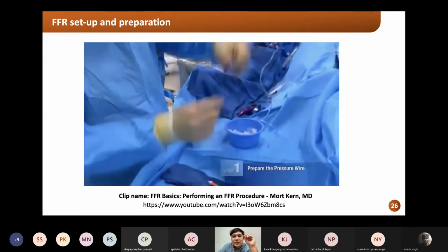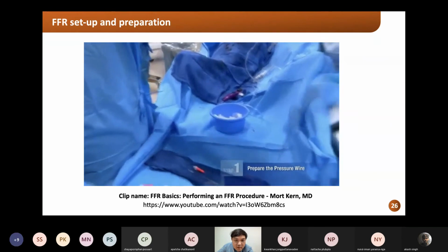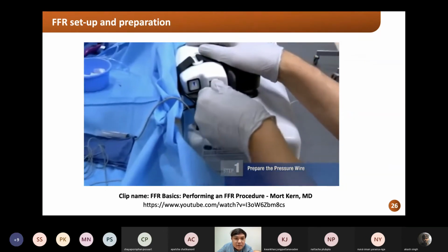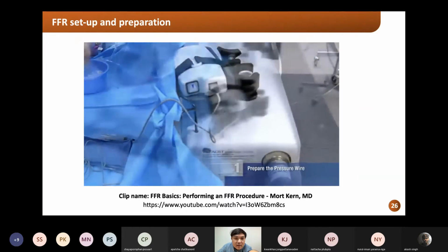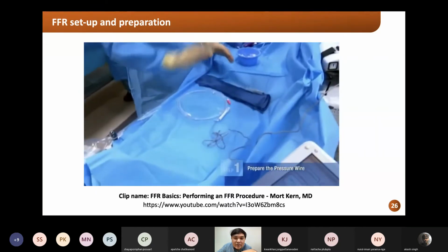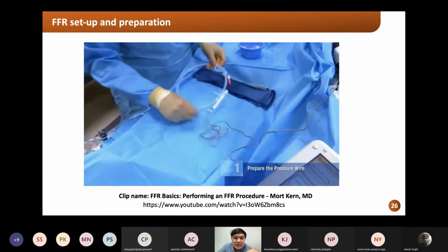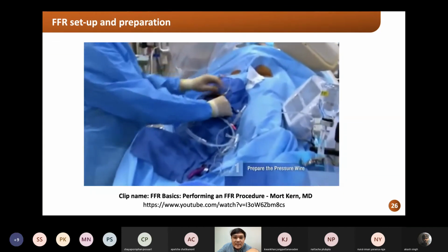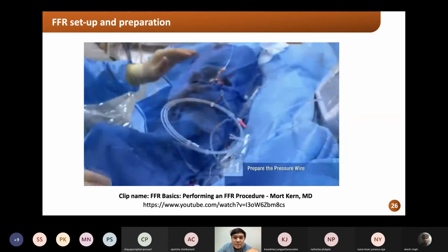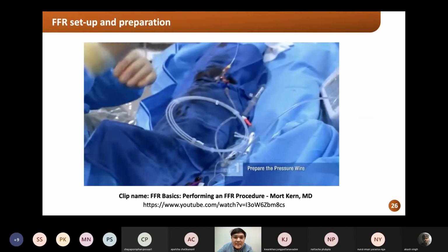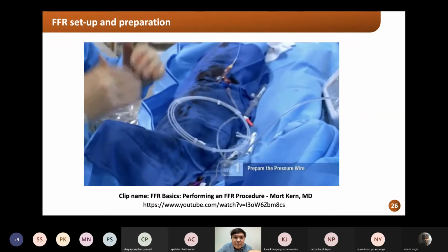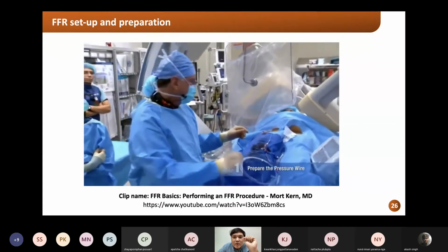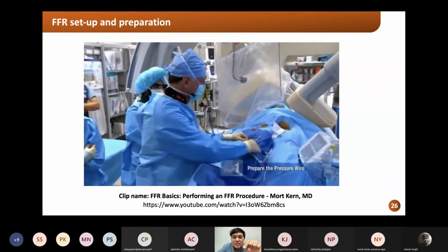After that, you have to secure the connector of that module and send this end of the line to connect to the instrument. After that, you will let the circulating technician zero the pressure, right? Zero to the air because it's located outside our body, so you can directly zero to the air now, prior to inserting into the patient.